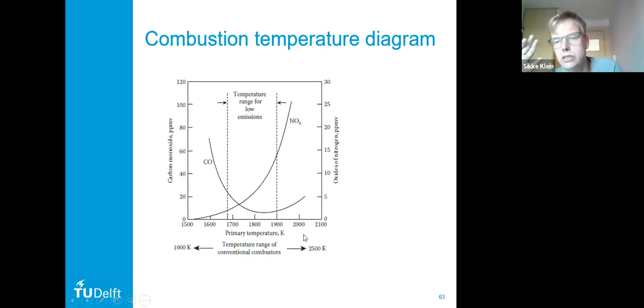If you look at the homework assignments and the other situations, this is also more or less linked to the turbine inlet temperature. So you have only a very limited range of stable temperatures where you have both low NOx and stable combustion. That's really the trick with premixed combustion. You have a very small zone of stable combustion, and that makes it quite a complex system to develop and to operate. But you get very effective NOx reduction in such a system.